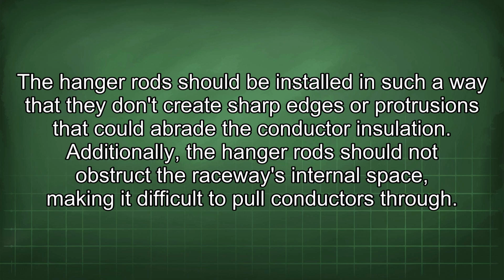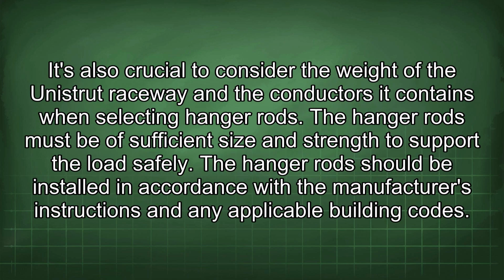Additionally, the hanger rod should not obstruct the raceway's internal space, making it difficult to pull conductors through. It's also crucial to consider the weight of the Unistrut Raceway and the conductors it contains when selecting hanger rods. The hanger rods must be of sufficient size and strength to support the load safely. The hanger rod should be installed in accordance with the manufacturer's instructions and any applicable building codes.